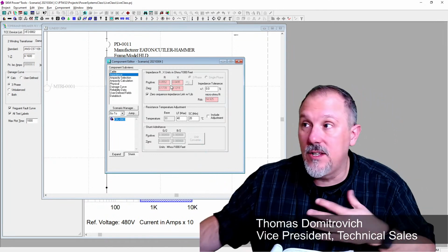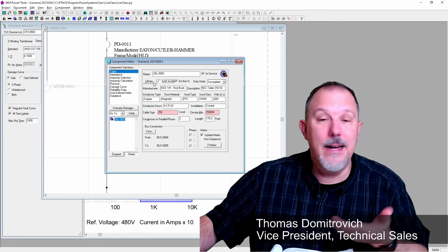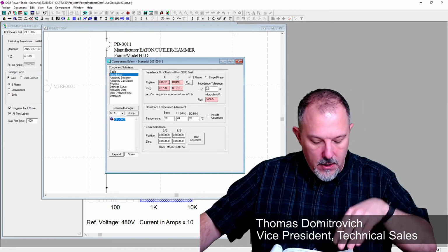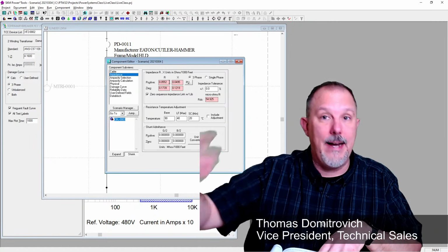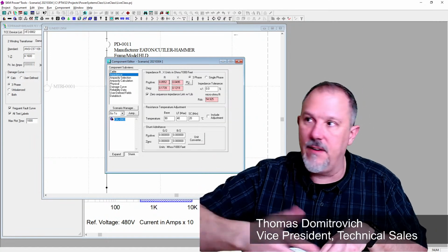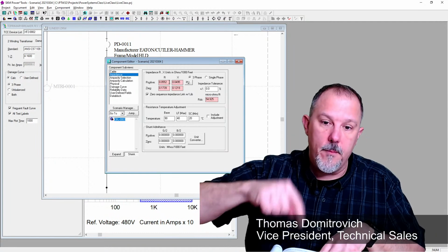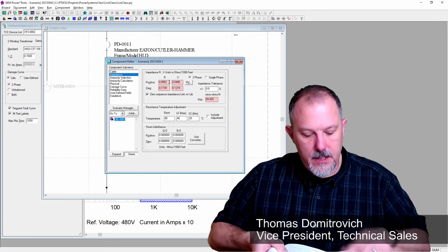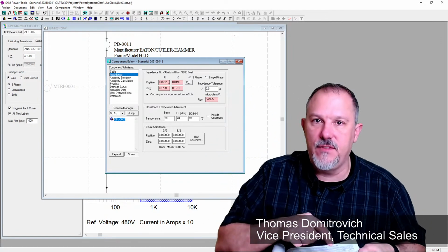So I'm going to override this. I unlink it from the library, and I'm going to just follow this. Now you can do whatever you want. You can use what's in your library, and that's probably preferential, or if you know from the manufacturer. I'm on Table 9 in Chapter 9 of the code, looking at the impedance values.